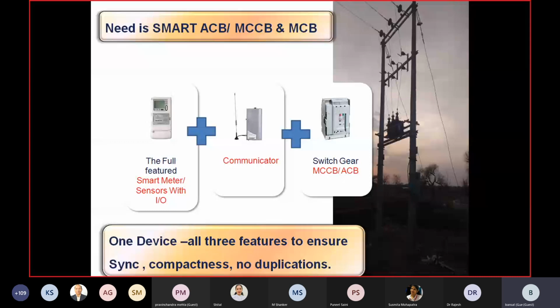So far we are using only the circuit breaker, but now what we are looking for is a circuit breaker with a complete meter built into it, with sensors and IOs. It has to be bi-directional communication, and integrated with the existing switchgear, which can be MCCB or ACB. So it is like one device. So far we have had ACB as a separate device, meter as a separate device, and a modem as a separate device. Here we are talking about all in one, so that there is proper synchronization, proper compactness, and no need of duplication.